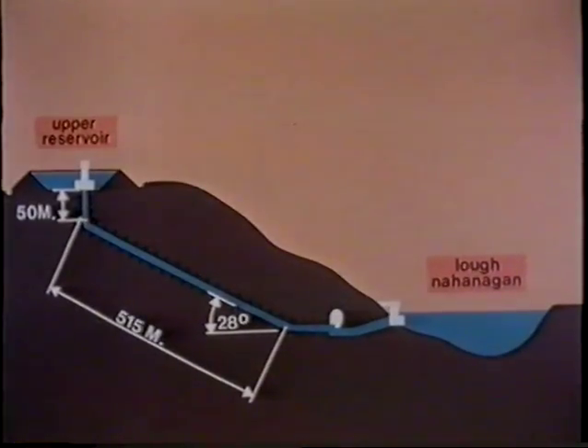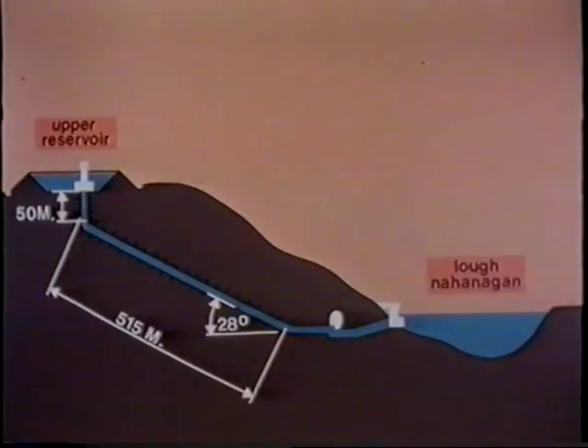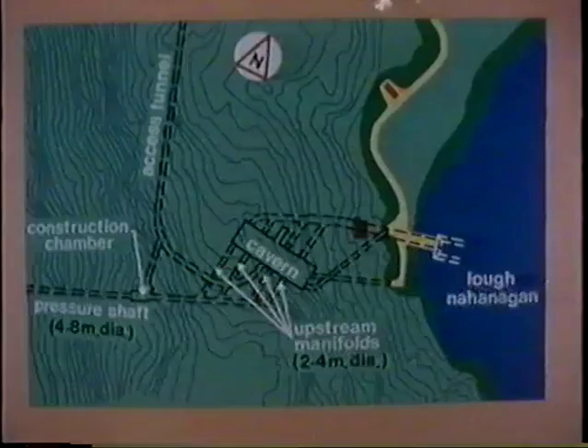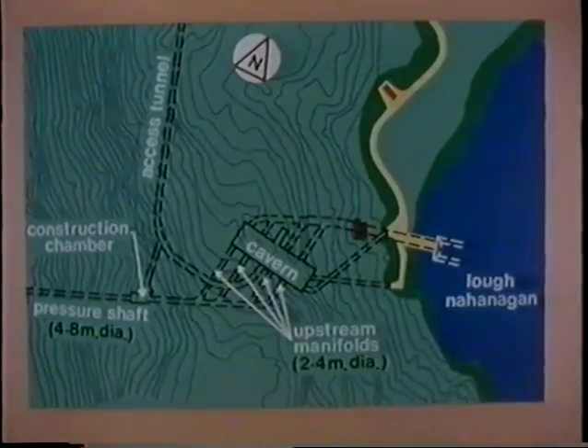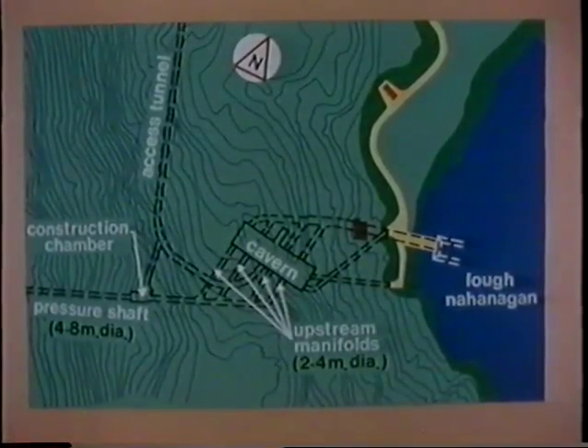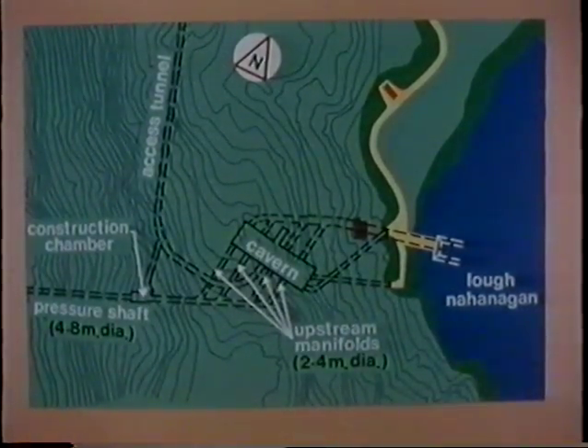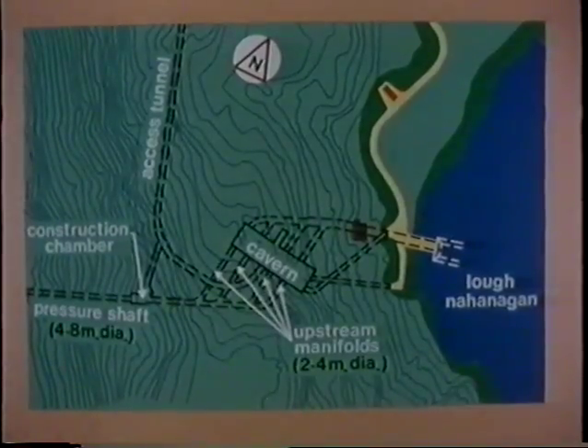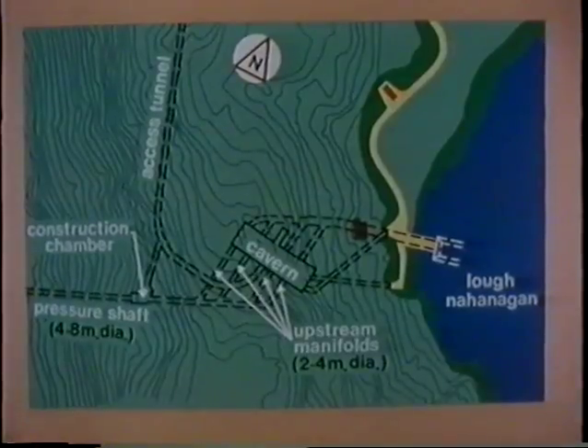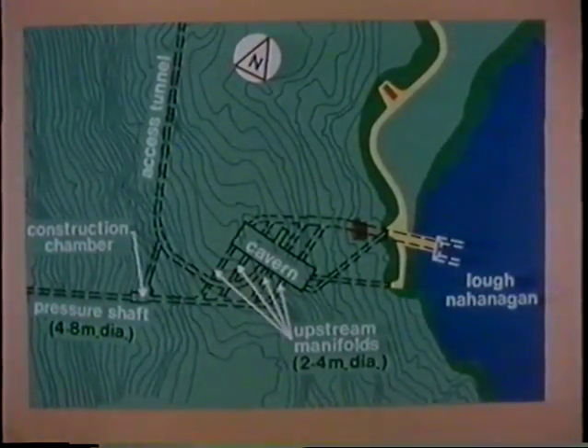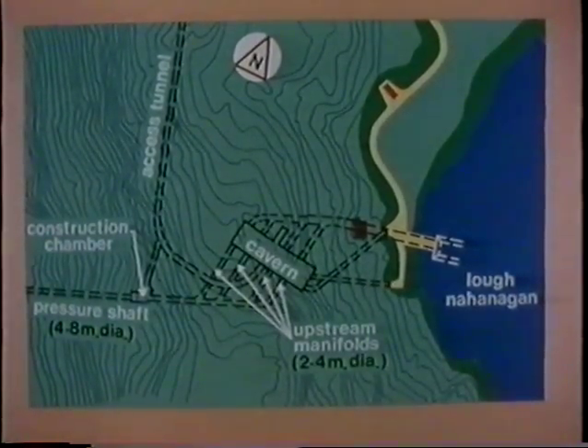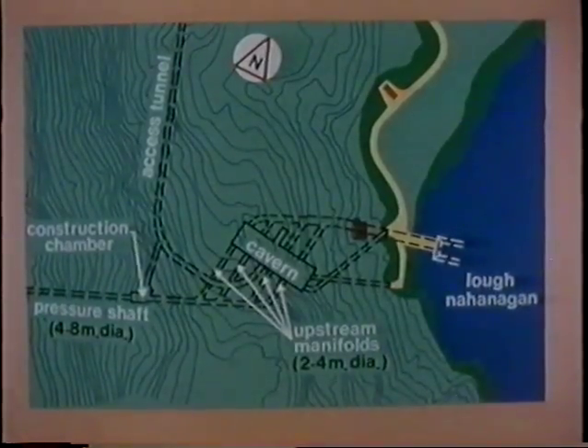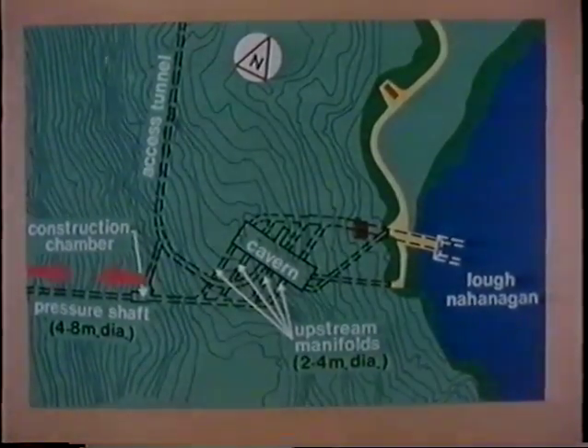The location of the cavern naturally affects the design of the pressure shaft. The penstock, 4.8 meters in diameter, narrows to 3.4 meters at the lower end, where it joins 4 manifolds which convey the high pressure supply to the turbines. Each manifold is 2.4 meters in diameter, and each brings reactions of 2,200 tons into the rock.